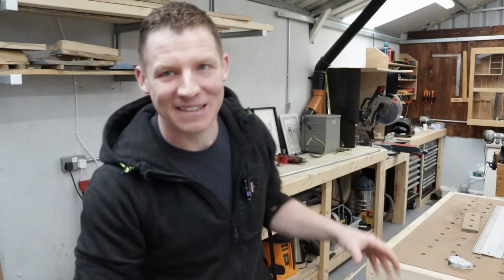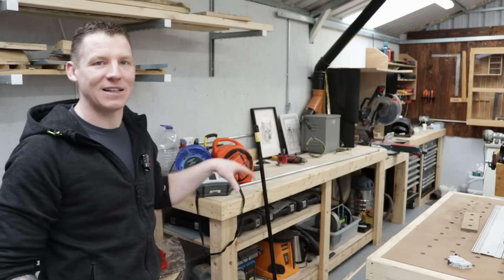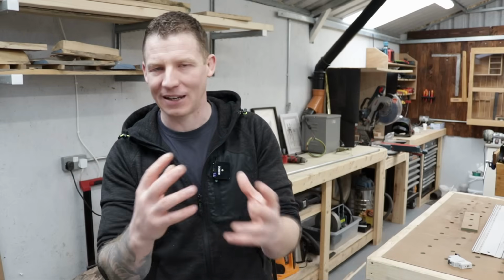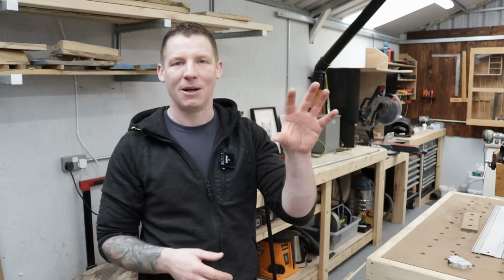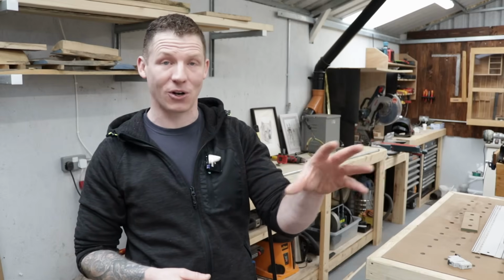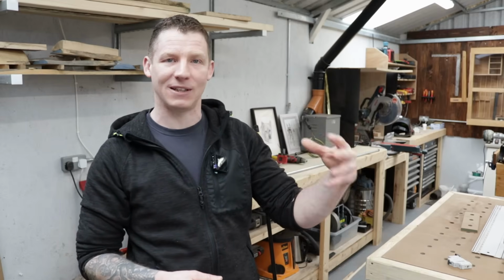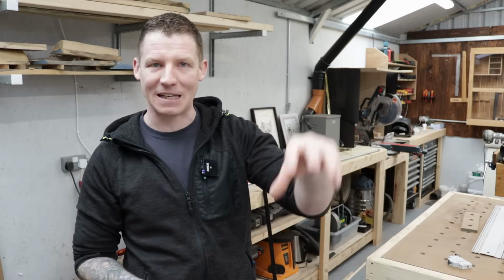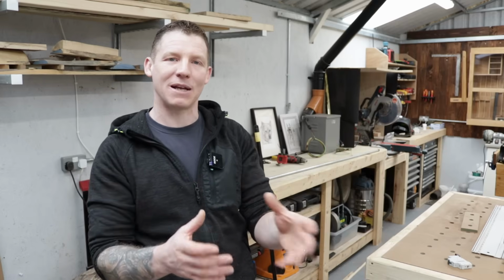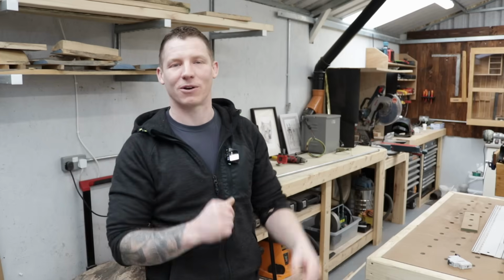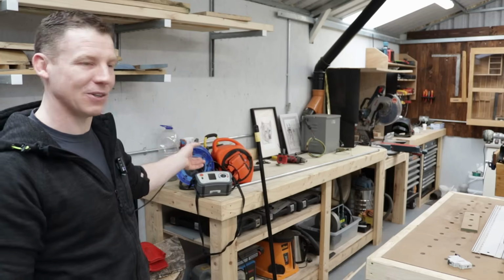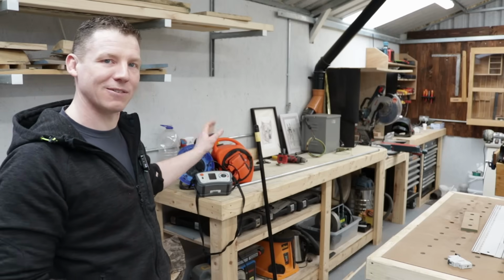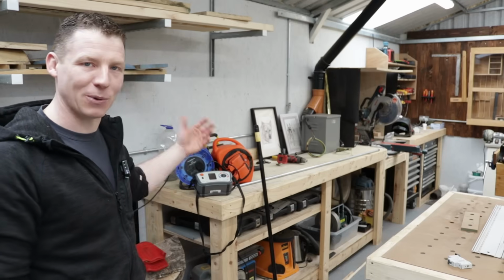Just wanted to illustrate the dangers of using extension leads. Adding an extension lead to an already long circuit can push it over the threshold of what that breaker needs to blow it out, and it's also just kind of kills 2 birds with the 1 stone there. So you can see the purpose of keeping your circuits short and possibly oversizing the cables for your circuits in order to keep the resistance down. So that's why your mains cable can be oversized, why you should keep all your circuits short, and why you should never use extension leads as a permanent solution. You could just potentially turn them into a heating coil.